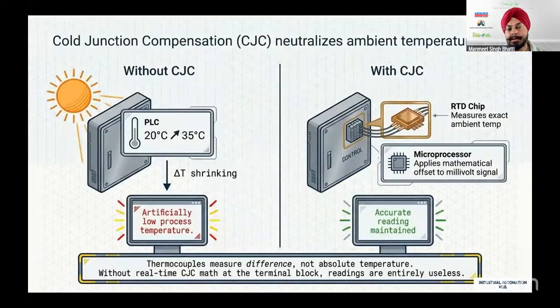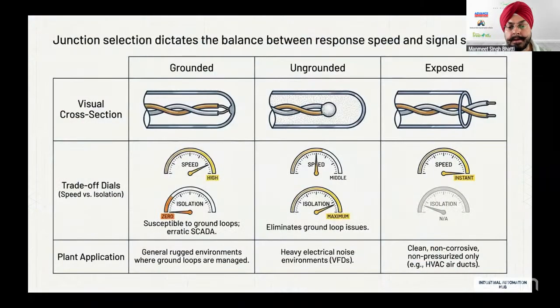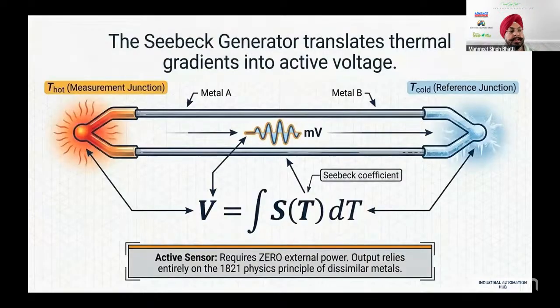Now, this is one area where people lose a lot. If you go to the old slide of this, I have shown you that because of the Seebeck effect, there is a temperature difference between a cold junction and a hot junction, and we get a millivolt, right? This is the way we started. Now, most of the temperatures are being measured from the hot junction because we are going for hot temperature. Very few we go for a lower temperature, but mostly it's the hot temperature. So we are worried about the temperature accuracy coming from the hot side. What we miss is basically the cold junction.